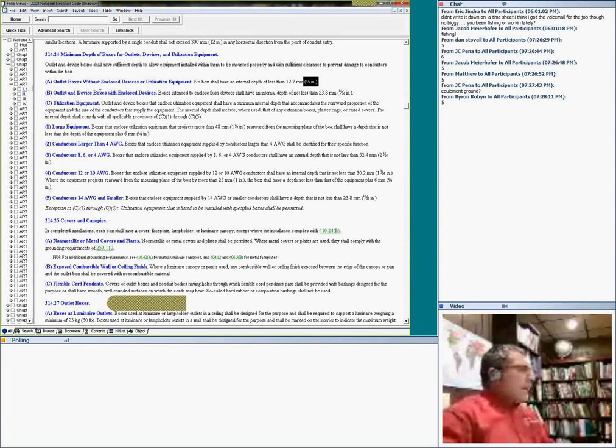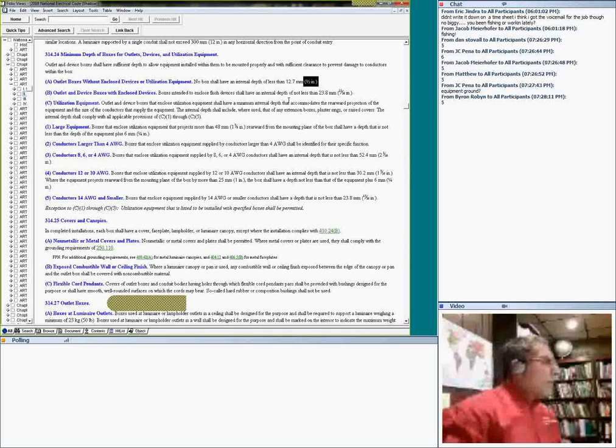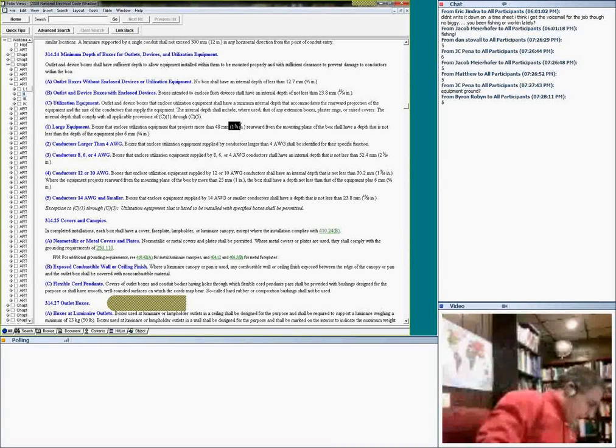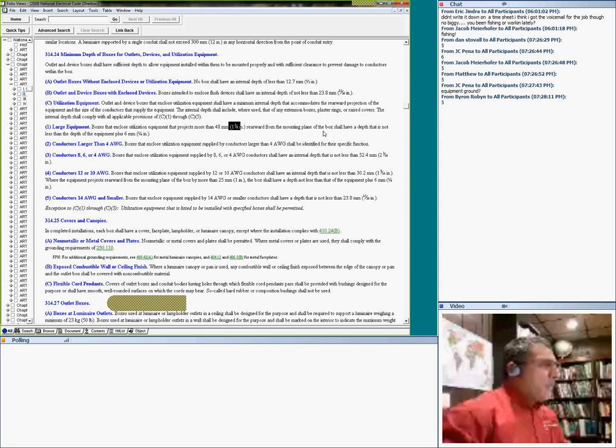Without a device, outlet and device boxes with enclosed devices: if you have to put a device in it, it has to be at least almost an inch deep. Utilization equipment: if you have to put utilization equipment in it, guys, look at that. If you're tying in large equipment, boxes that enclose utilization equipment that project more than an inch and 7/8 of an inch from the mounting plane of the box shall have a depth that is not less than the depth of the equipment plus a quarter inch. So they want you to get even an extra quarter.